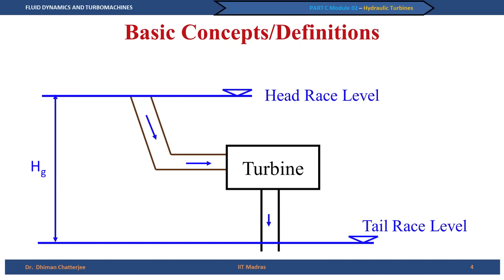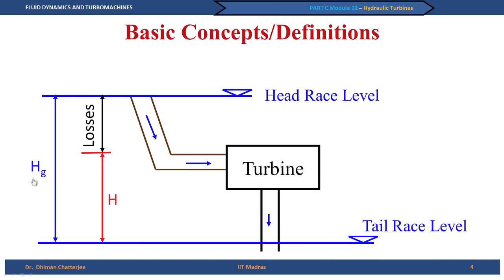However, whenever there is flow, there will be losses associated with it — approach losses, exit losses — and hence what is available to the turbine for power extraction is not H_G. What is available is the energy at the fluid before it enters the turbine minus the energy as it leaves. This is given by H_net, or H, which we call the net head, as opposed to H_G the gross head.